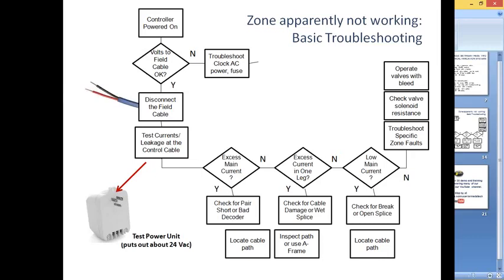But you use this little power unit to apply power to both leads of the main control cable, and it allows you to do the same measurement with the clamp meter. Do I have too much current flowing? Is there excess current on one side of one of the wires and not on the other? Is there a very low current, meaning I've probably got a cut up ahead somewhere and some of the decoders have been isolated and they're not consuming as much power as they should?